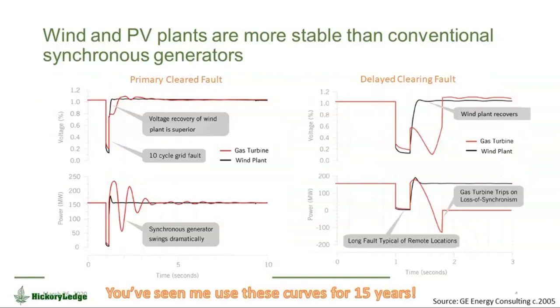So we go forward. Those of you who've been listening to me lecture for seemingly a really long time will recognize this slide, which I've been using since 2005, from my GE days. And this is a radial system of almost exactly the topology of my cartoon. It happens to be a simulation of the Colorado Green wind farm, but you don't really care. It's 160 megawatts. And this is, all things being equal, a wind plant versus a synchronous machine of the same loading and rating. And again, you'll recognize all of this stuff. On the left is a primary cleared fault, and the synchronous machine in red swings and stresses the stability of that system. The black curve is the wind plant, which behaves radically different. So what I want to do here is dive into the basics of that behavior and where we're coming from and why it looks different with synchronous, without synchronous machines.